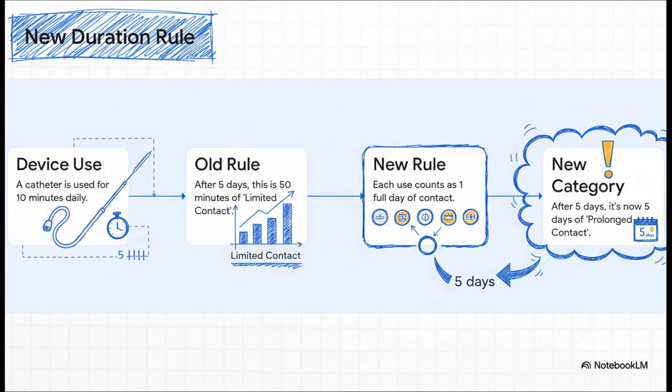But under the new rule, any contact within a 24-hour window, doesn't matter if it's one second or one hour, it counts as a full day. So that same device is now suddenly categorized as five days of prolonged contact, which can trigger a whole new world of evaluation requirements. It's a game changer.